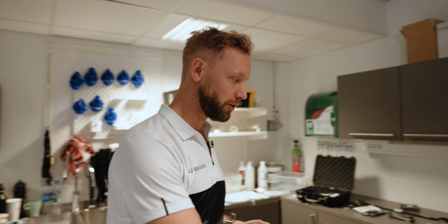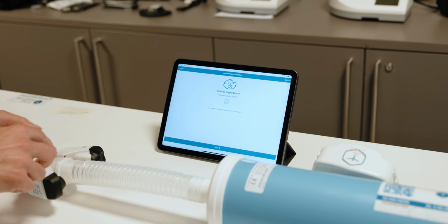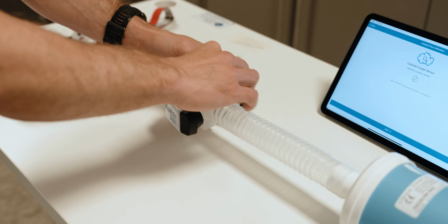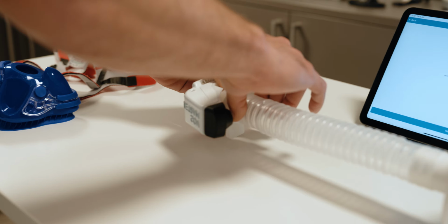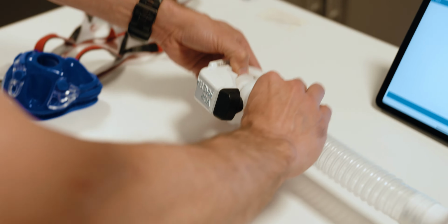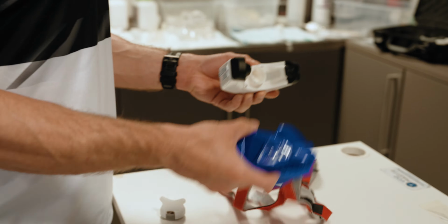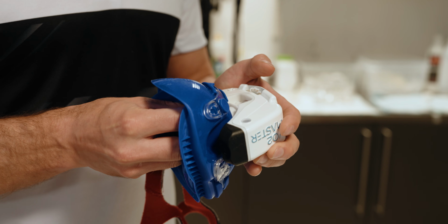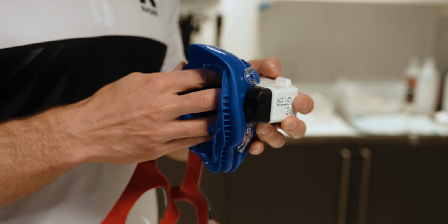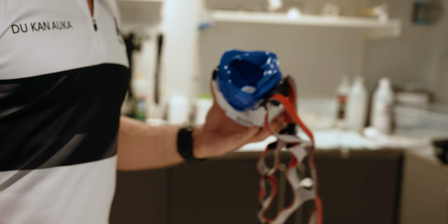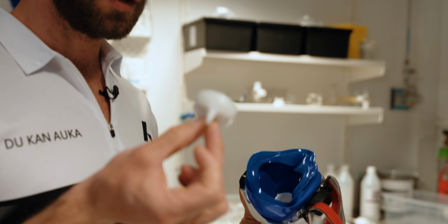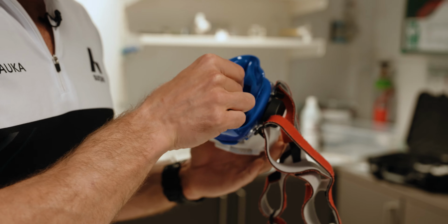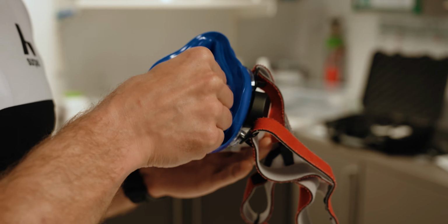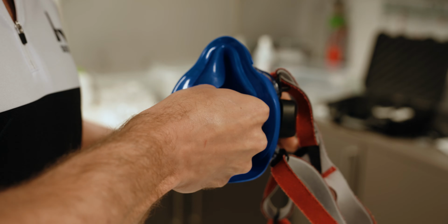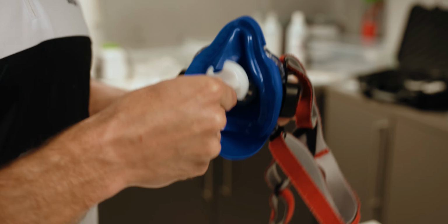All right, so we're ready to assemble the unit for testing. The oxygen calibration went through. When I take this off, I make sure that I don't slide the user piece inside. So I kind of gently touch the inside, and then I open it, take off the silicone spacer, and now I can put on the mask. I try to shake the analyzer as little as possible and be fairly gentle. Now the mask is on. And with this nut, I can now assemble it on the inside. Make sure you press the cap on all the way in and then turn it until you meet resistance to make sure that it doesn't fall off during exercise.